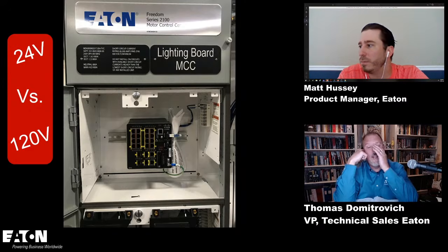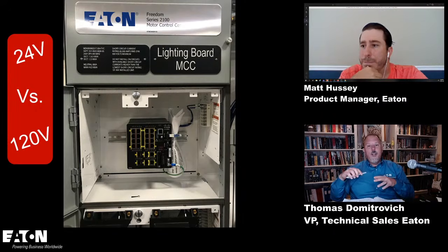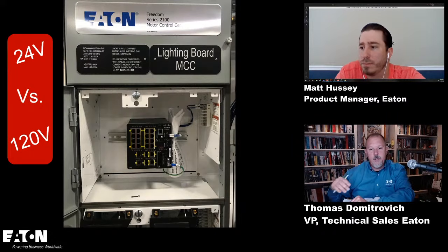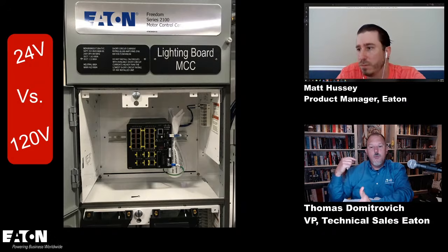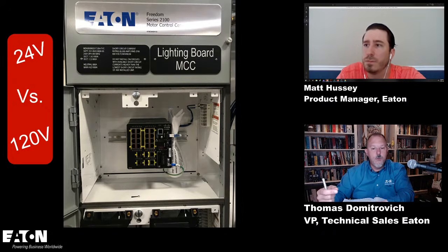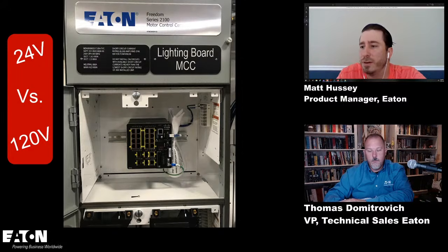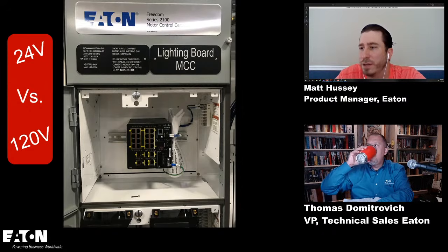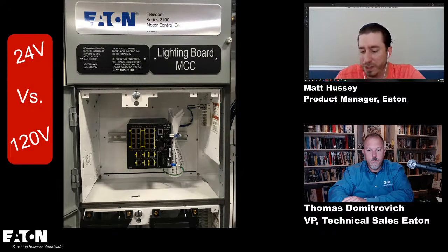Excellent. And so the other thing in there is I know that anything we can do with lower voltage increases safety because I'm below the shock thresholds and things like that, right? So why don't we do more 24 volt DC or AC or whatever control in these motor control centers? Usually, in a lot of cases, you're trying to provide continuity for the control applications, and a lot of times, remember, Tom, MCCs might be located hundreds of yards away from the process control systems that control them. And so one of the challenges we have to overcome is voltage drop for a lot of the coils, especially as you get up in size for contactors and things like that.